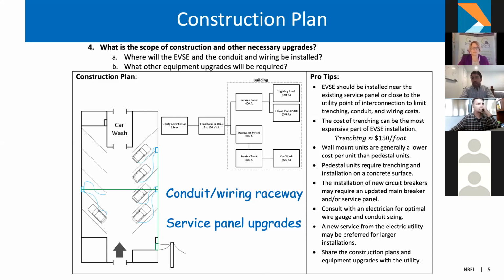So when you're planning all of this out, you want to look at all the loads that are going to be consumed at a given point in time. If you're charging devices at night, you might not need to consider the lights if people aren't using the garage. But if they're going to be there whenever the lights need to be on and the vehicles need to be charging, then you'll know that if the lighting load already occupies about 150 amps, it won't leave a lot of spare capacity for new EVSE to be installed.